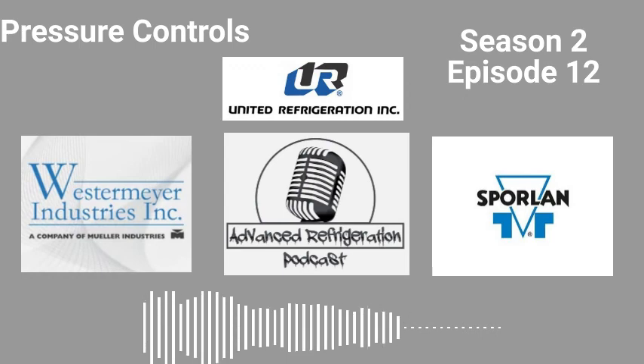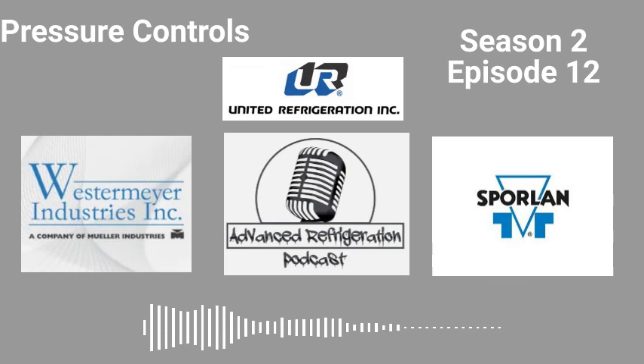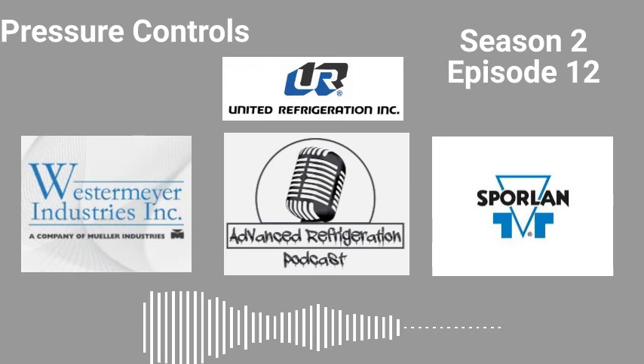How about the CO2 racks you're doing with all the transcritical — is there anything different or special with those versus conventional? Generally, we don't really have low-pressure controls on the medium temp — it's all computer controlled. Some of the Aldi's do have low-pressure controls on the low temp, and we'll have standard high-pressure controls on the low temp discharge. We will have high-pressure controls, but they're usually the Emerson encapsulated black PSK ones, and Bitzer has their own that they use all the time.